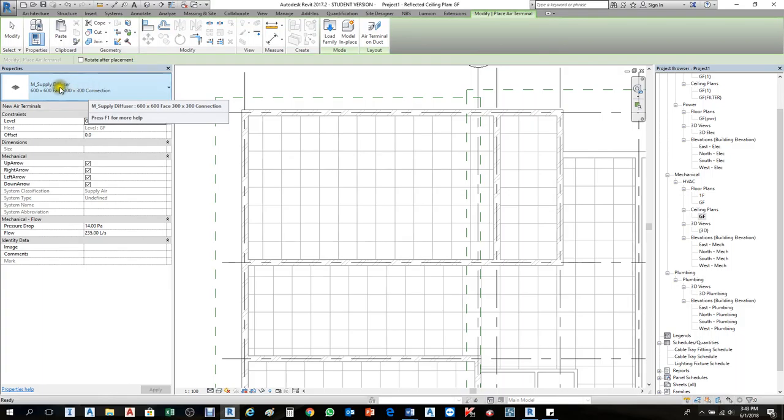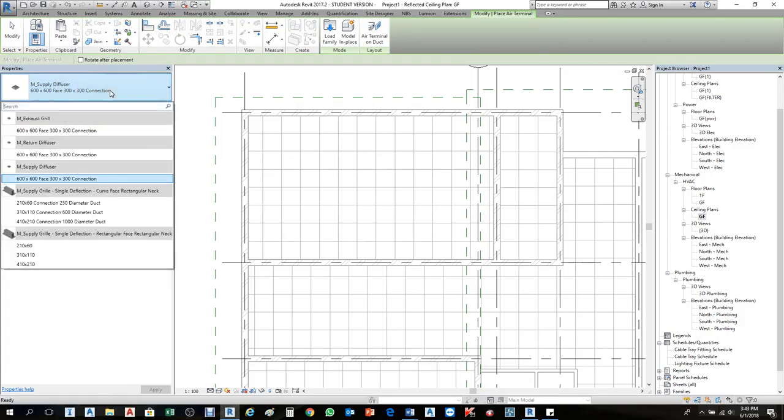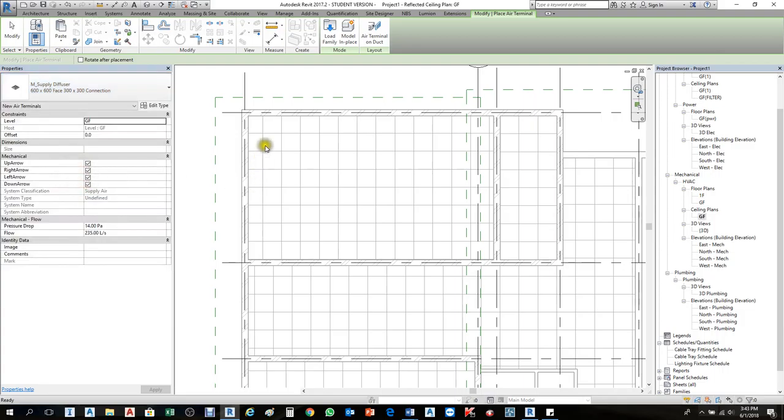Now, when you click the air terminal, in this Properties palette you have a choice of what kind of air terminal you want. For exhaust grill, you have return and supply. So it's up to you, whatever you want to put, you can change it anytime. Here, 600 by 600 face, 300 by 300 connection, which means this one is 600 by 600 to align with the ceiling, and the connection outside, the output, is 300 by 300.